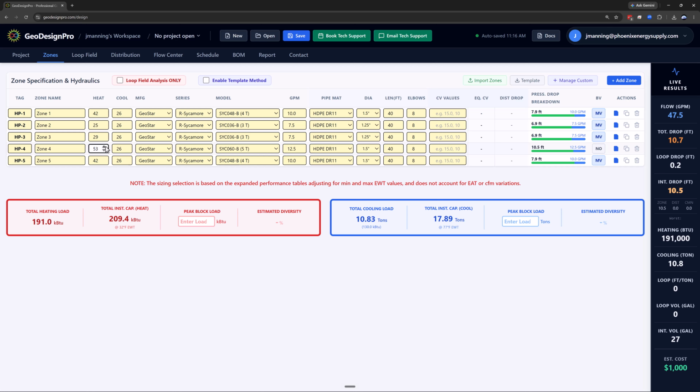So the program will automatically select the heat pump that meets the most demanding load, either heating or cooling. In this particular case, we're also going to change that Sycamore to an OptiHeat. And you'll see the OptiHeat is flagged at 6.66 tons because we want it to be at a higher flow rate. The last heat pump is an Aston water to water. Might be serving a garage radiant system or something.